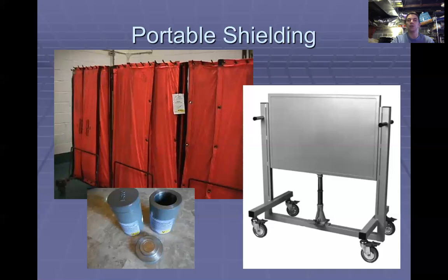They can be set up so they're not in true, we say radiation isolation, but we don't want them to be in true isolation. So a larger room may have a small sofa in it that would allow somebody to come and visit with the patient while also having a safe dose rate in that area. That's something that we would set up, we would survey, and then we would have a consultation with the patient and the family to explain that this area is safe. A lot of other areas in this room are not safe to spend extended periods of time.